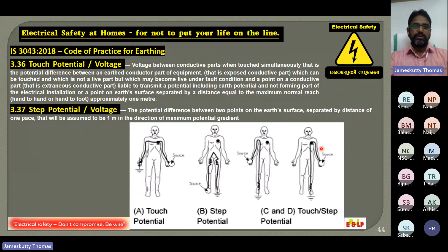Okay, now here I am trying to explain the potential gradient created from a downed conductor. If the line voltage is 11 kV, the conductor will be the center point. Just like ripples, voltage bands, here it is the band. Voltage ripples will be created around the fallen conductor. Say here it is 11 kV, here it is 10 kV, 9 kV, 8 kV, etc.